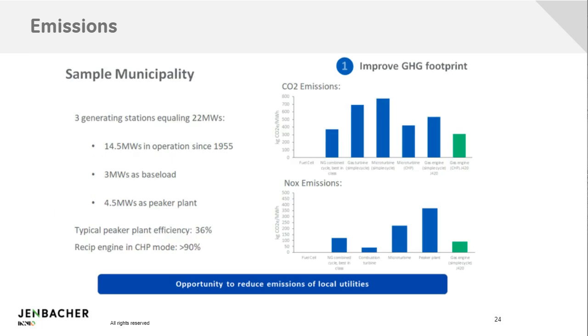Using an example of a municipality, we're looking at 3 generator stations with a total output of 22 megawatts. The breakdown is 14.5 megawatts of older generation, with 3 megawatts as base load and 4.5 megawatts as peaking plant operation, totaling 22 megawatts, averaging 36% efficiency as shown in an earlier slide. In this case, we're comparing that to a typical recip engine in a CHP mode.